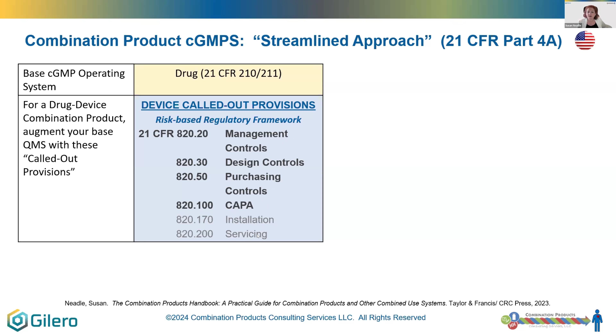So very quickly, a brief description of each of those. Management controls are those to ensure that the top level corporate management has a commitment to quality. So they're providing adequate resources and making sure that the quality system is functioning the way it needs to. Design controls is about controlling your design process, very similar to the concept of quality by design on the pharmaceutical side, but it's to assure that the device and the combination product will meet user needs, intended uses, and specified requirements. Purchasing controls are establishing procedures for supplied products and services. And most companies that are manufacturing combination products are at least purchasing one of the constituent parts for their combination products. So it's got plans for outsourcing, selection of your suppliers, supplier evaluation and acceptance, approving your suppliers, having quality agreements in place.